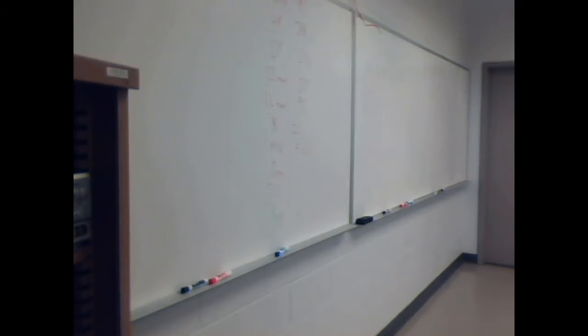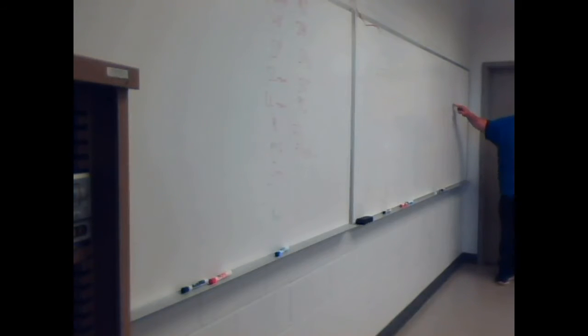But the formula, and again I'm asking, actual suction line temperature or pressure? Actual suction line temperature, minus, and with that temperature we subtract the saturated suction temperature, which is the correct name of it. How do I get saturated suction pressure? I take the suction pressure and convert it with the chart on your gauges. What you got up there, Clay? Actual suction line, I'm sorry, it's actual suction line minus saturated suction temperature.